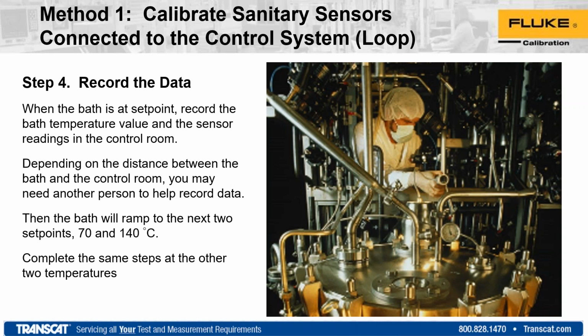And typically, for these, with the 0.1 accuracy, you're going to be testing sensors with a larger uncertainty, maybe potentially plus or minus 1 or even plus or minus 0.5. Most of the time in a process, you're carrying some sort of test uncertainty ratio, and in the industry the rule of thumb is 4 to 1. So that's something to keep in mind on your uncertainty. There are many methods, whether you're doing it right to a display or using a reference. There's a couple of ways to go at it.